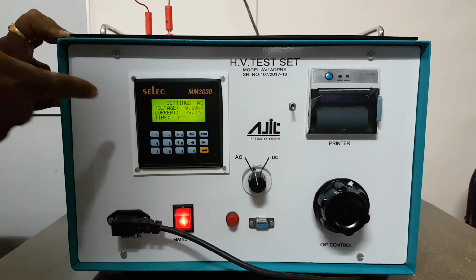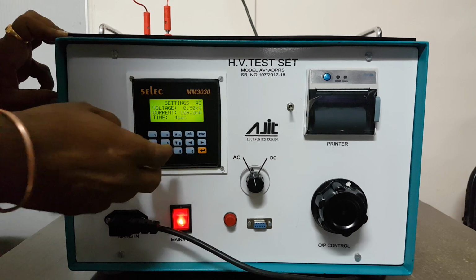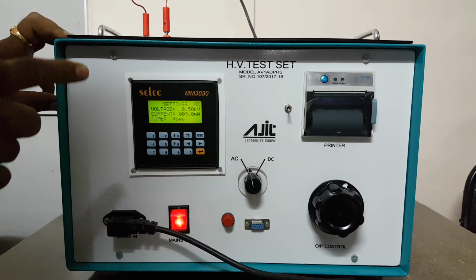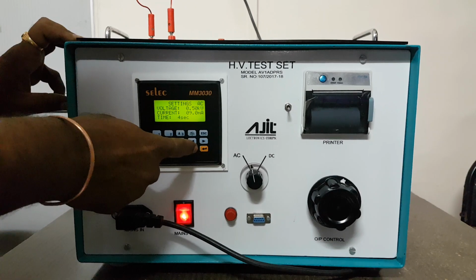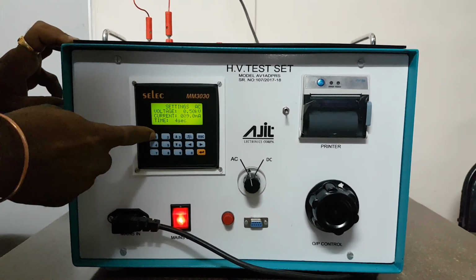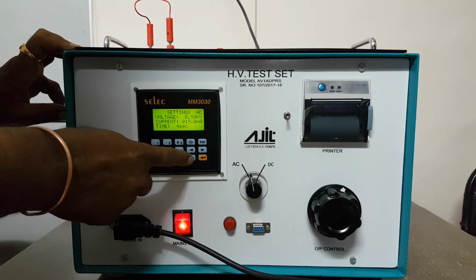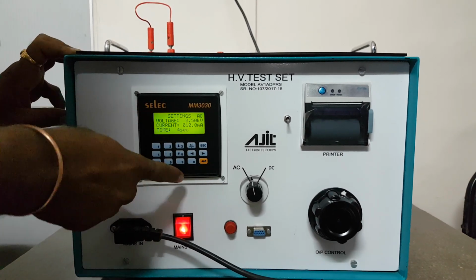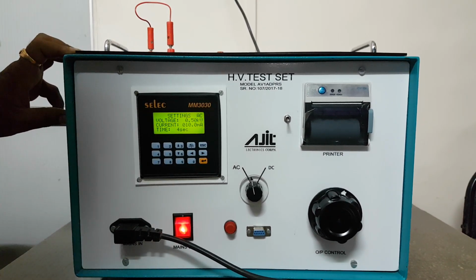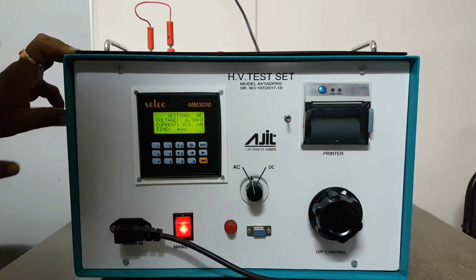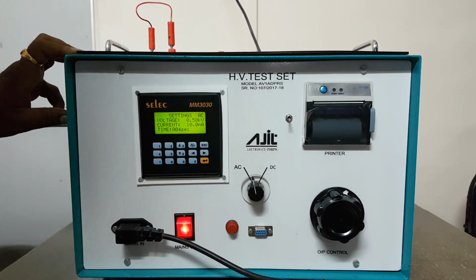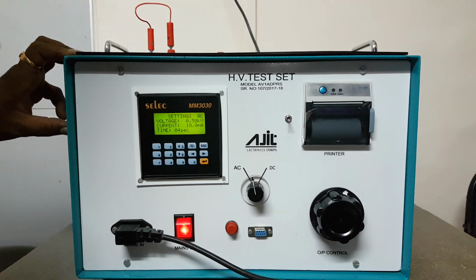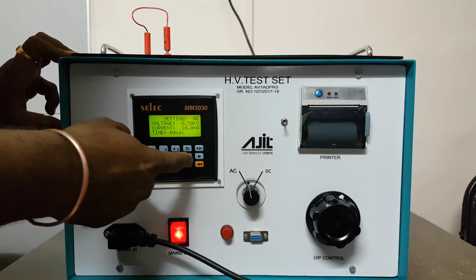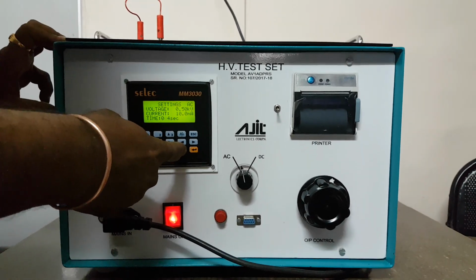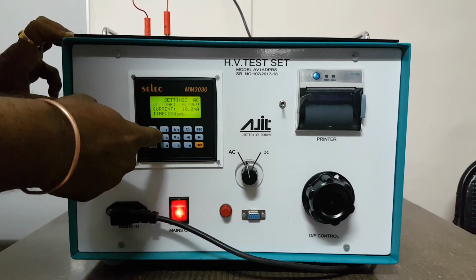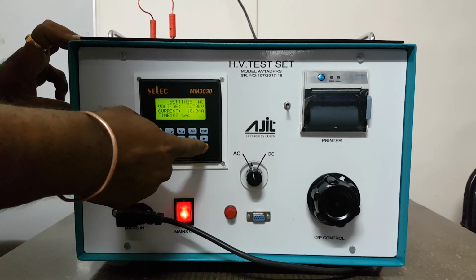Then it will ask for the current limit setting. If we want to change it from 9 milliampere to 10 milliampere, press 0, now press 1, and make this 0, again the decimal also 0. Once all the 4 characters are set, press enter. Now the time, this is the test duration. Here it is 4 seconds. If we want to make it 5 seconds, we can do it like this and press enter.